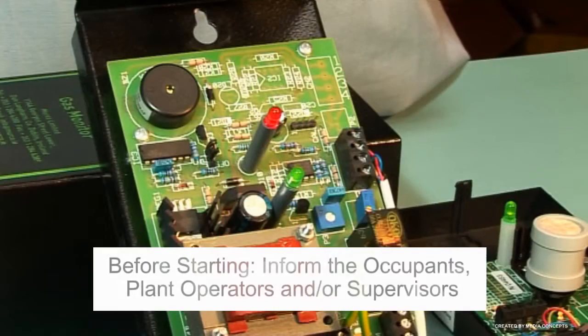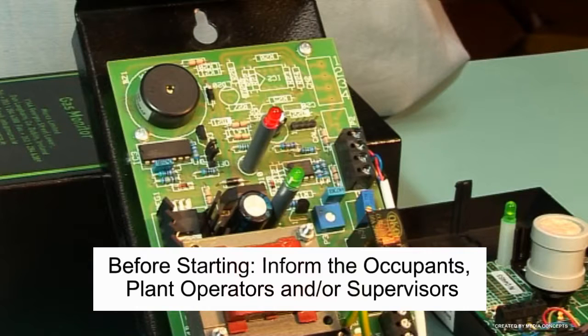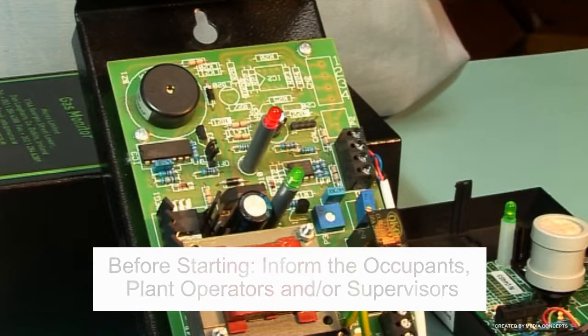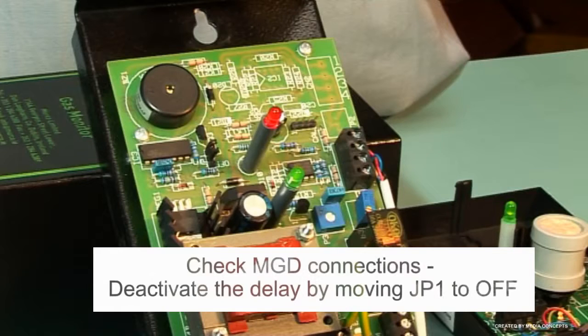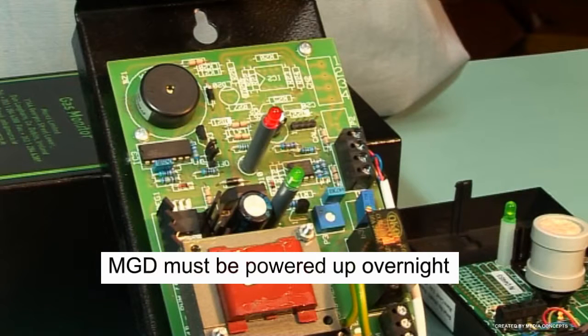Before starting, inform the occupants, plant operators and/or supervisors of the test. Check MGD connections to external equipment and disconnect if required. Deactivate the delay on the level 1 system by moving jumper JP1 to the off position. Before performing your test, the MGD must be powered up overnight.